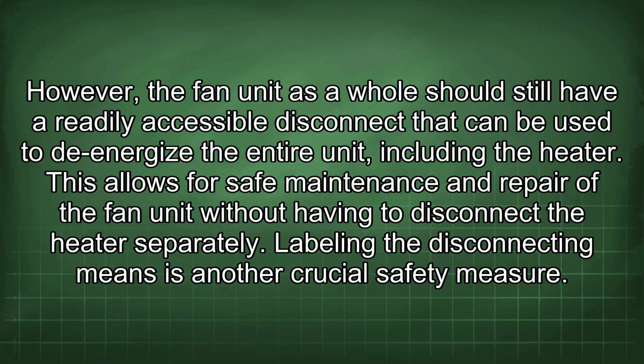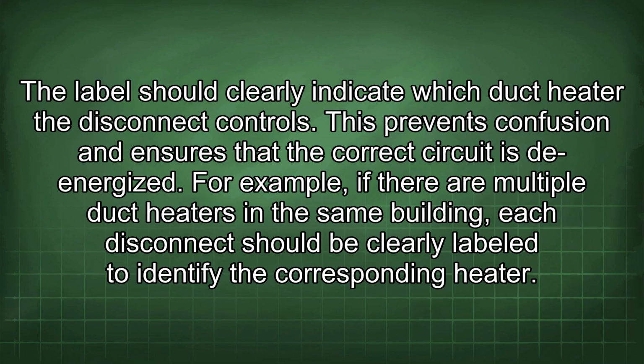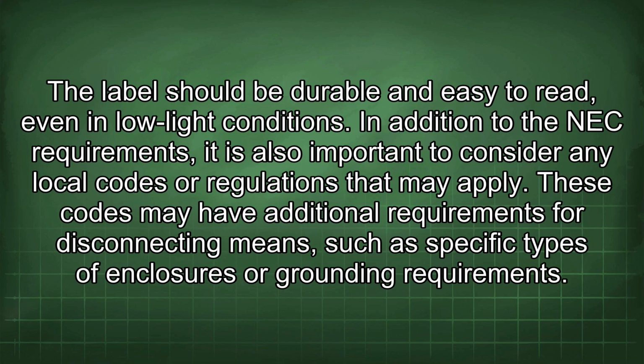Labeling the disconnecting means is another crucial safety measure. The label should clearly indicate which duct heater the disconnect controls. This prevents confusion and ensures that the correct circuit is de-energized. For example, if there are multiple duct heaters in the same building, each disconnect should be clearly labeled to identify the corresponding heater. The label should be durable and easy to read even in low light conditions.